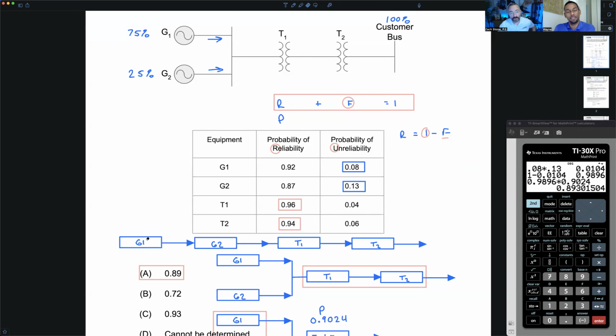So now, for example, if I lose generator number two, maybe I can still supply 75% of the customer load, but if the problem requires supplying the entire customer load, we've lost that in this case. That's why we would model it in series in that scenario. Okay, that makes sense — that's what I was missing earlier.